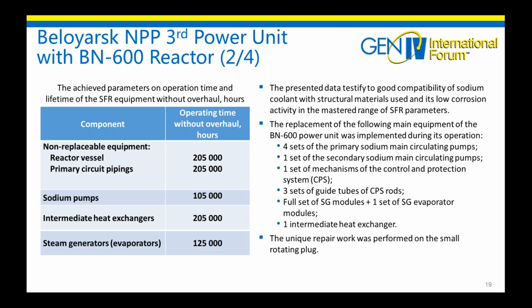The replacement of the following main equipment of the BN-600 power unit was implemented during its operation. So it's 4 sets of the primary sodium main circulation pumps, 1 set of the secondary circulation pump, 1 set of the mechanism of the control and protection system, 3 sets of guide tubes of this protection system, a full set of steam generator modules, plus 1 set of steam generator evaporator modules, and 1 intermediate heat exchanger. Unique repair work was performed on the small rotating plug during its life.